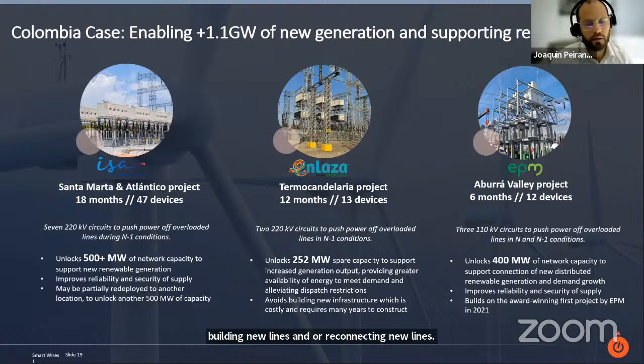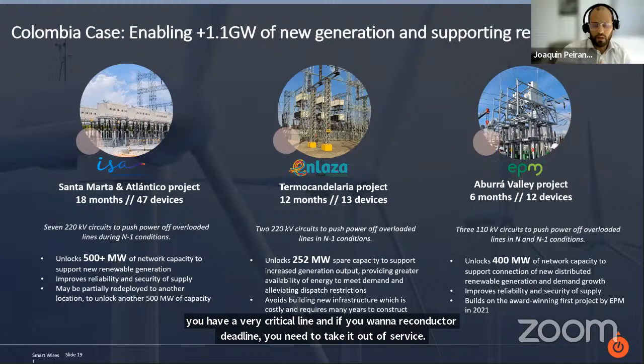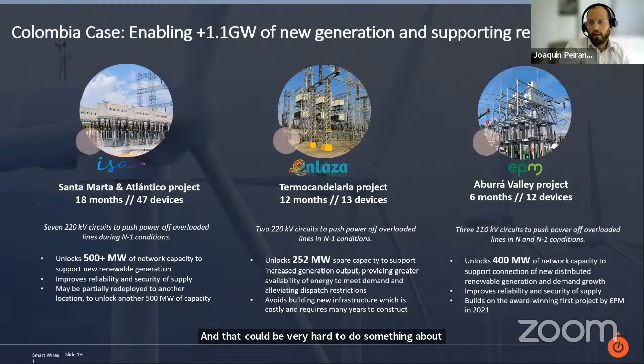Sometimes that's something very important. Theoretically, it makes sense to build new lines or even change the conductors in some cases, but there are two main challenges that utilities have. One is permitting, especially building new infrastructure and acquiring new right-of-ways in urban areas. The second is the outage. Sometimes you have a very critical line, and if you want to reconductor it, you need to take it out of service, which can be very hard to do, sometimes making the project not feasible.